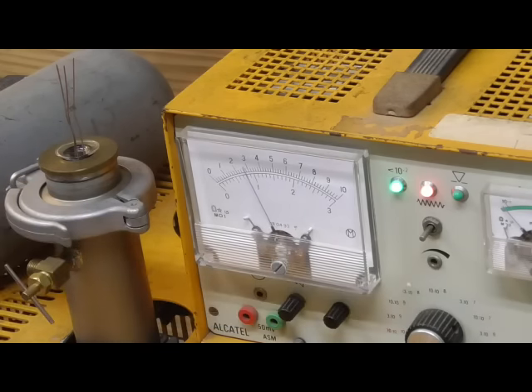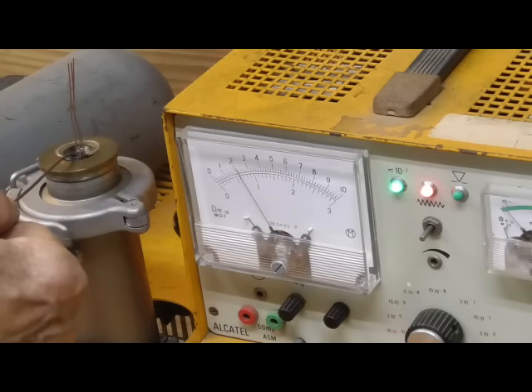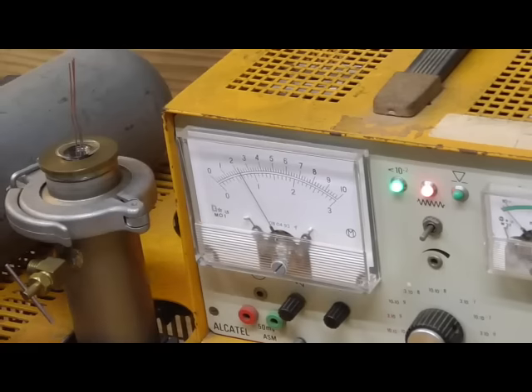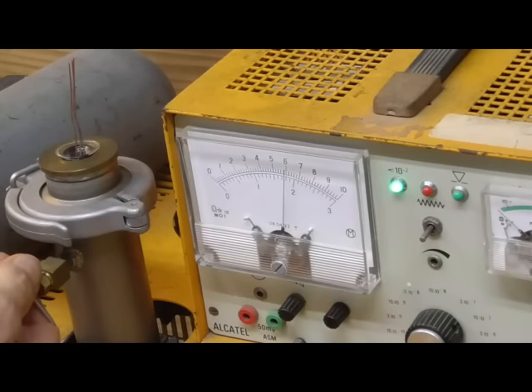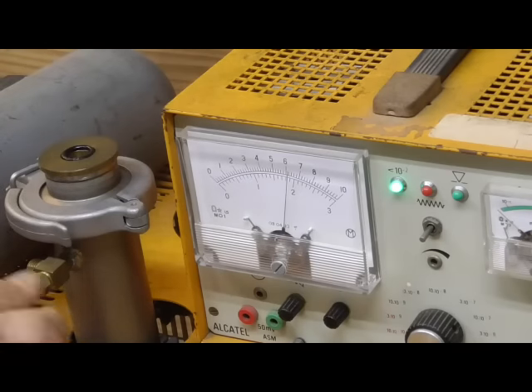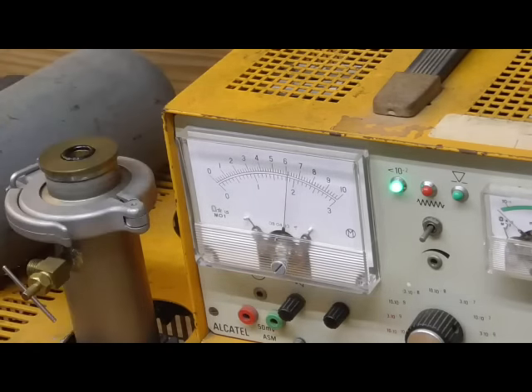That's a fake reading there. We got the helium there, but it's going down. It's not continuing to go up. It would continue to go up if we had a leak. All right, we're okay on it. So we got a good seal ready to use.